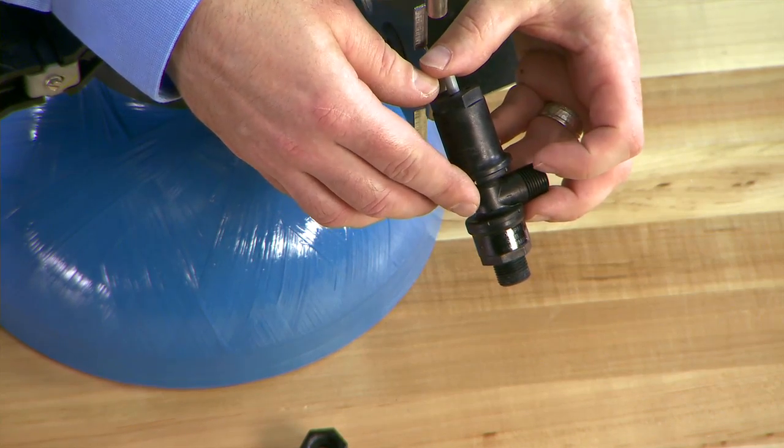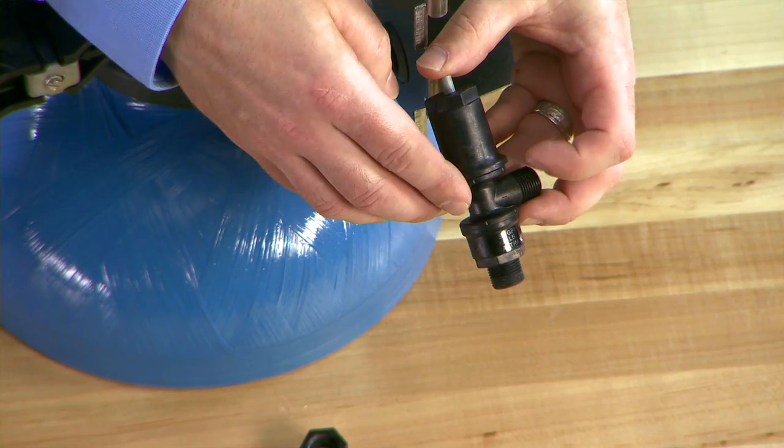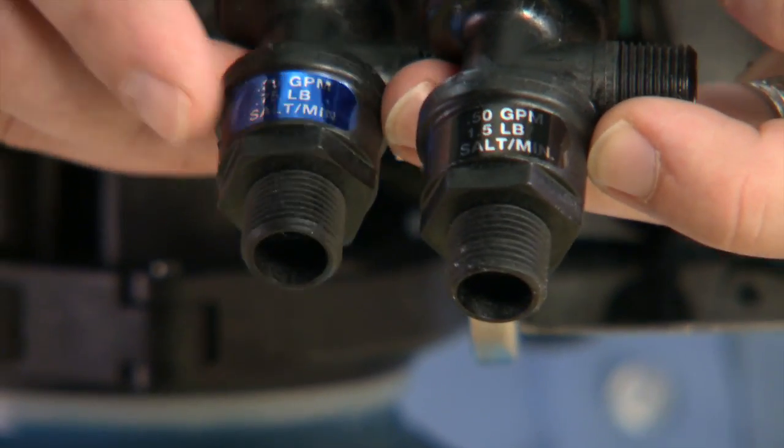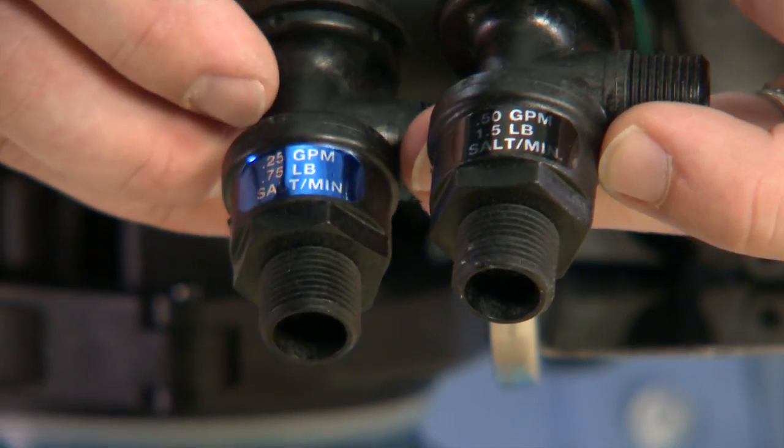This is our plastic 1600 brine valve. This particular unit is rated for 0.5 gallon per minute. If you need to replace the valve, please make sure to match the brine line flow control.